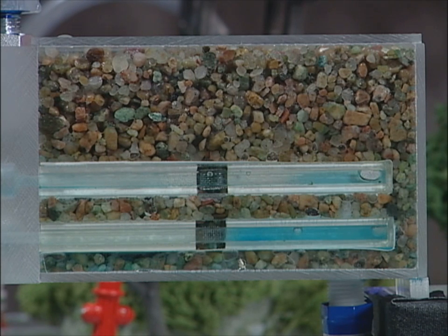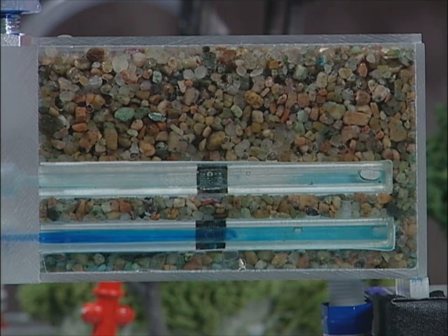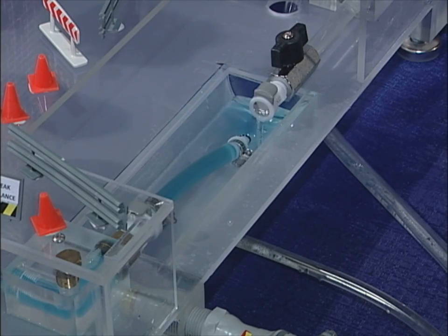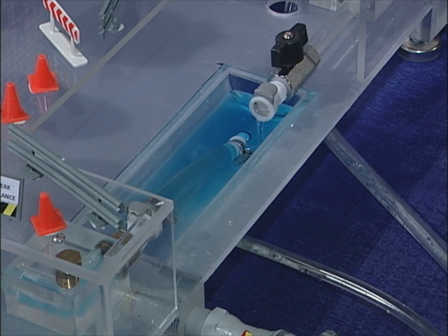When normal flow conditions exist, water under pressure flows out of the drinking water pipe and slowly flows into the surrounding area. The water may mix with the leaking sewage at a lower elevation. With sufficient positive water pressure in the drinking water line, none of this contaminated water can make its way into the system. If, however, there is a main break, dropping the pressure in the line, valves above and below the broken line will be shut off for repairs.